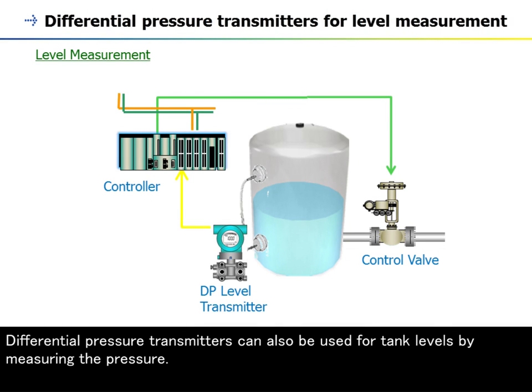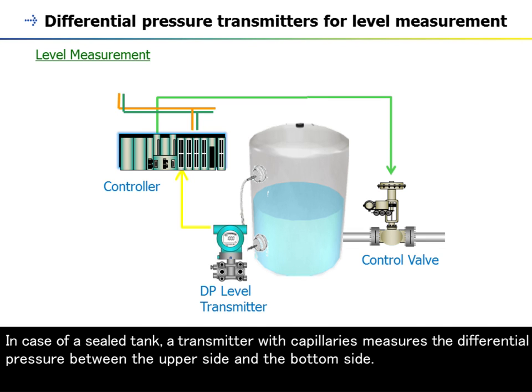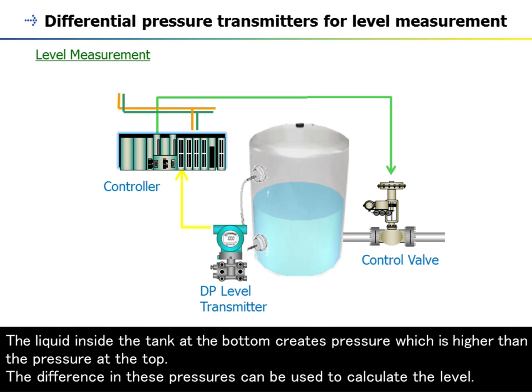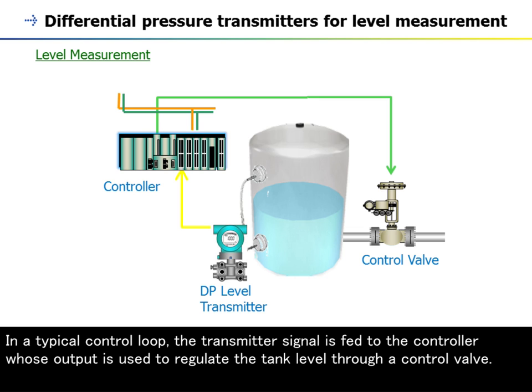Differential pressure transmitters can also be used for tank level measurement by measuring pressure. The transmitter is installed at the bottom of the tank whose level is to be detected. In the case of a sealed tank, a transmitter with capillaries measures the differential pressure between the upper side and the bottom side. In the case of an open tank, the transmitter measures the differential pressure between the liquid inside the tank and the reference atmospheric pressure. In a typical control loop, the transmitter signal is fed to the controller, whose output regulates the tank level through a control valve.